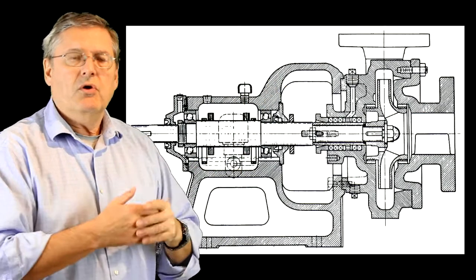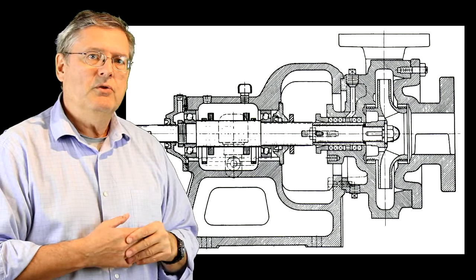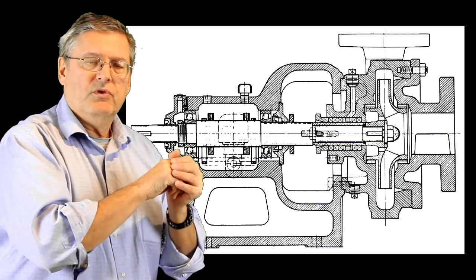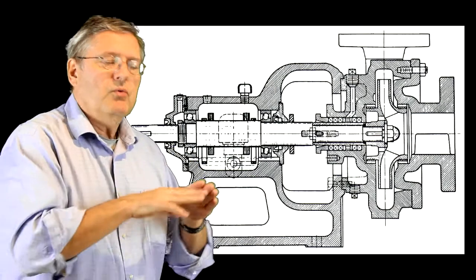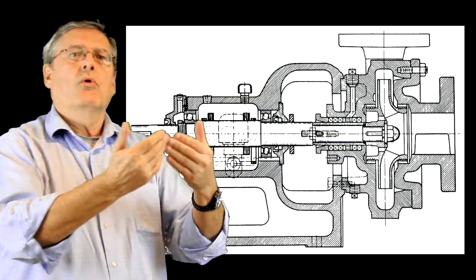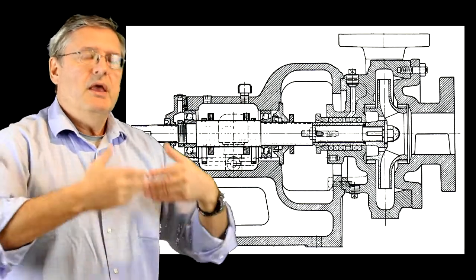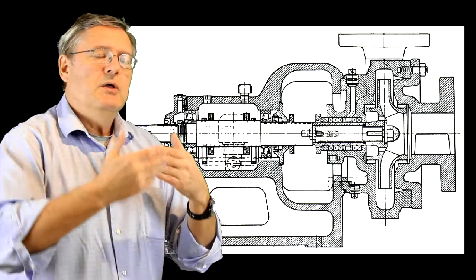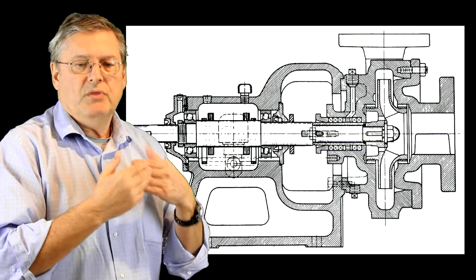The seal is also called a gland. The way the seal works is that higher pressure water is pumped in through the seal and that water will make its way into the pump or leak outside of the pump. This is how we ensure that we have a seal, in other words that the material in the pump stays within the pump.